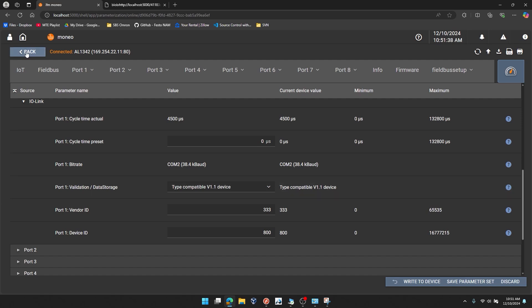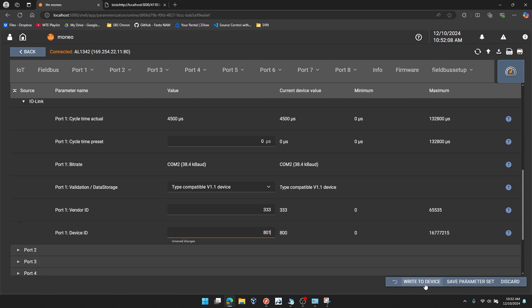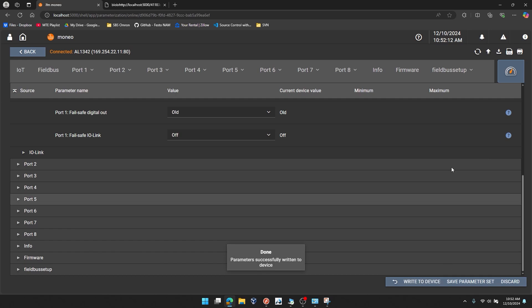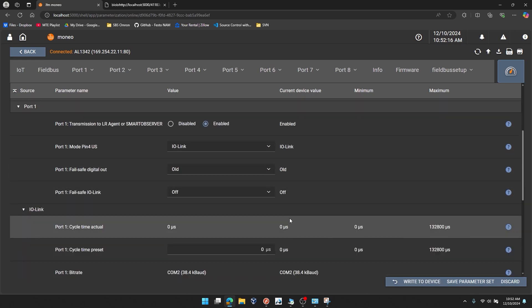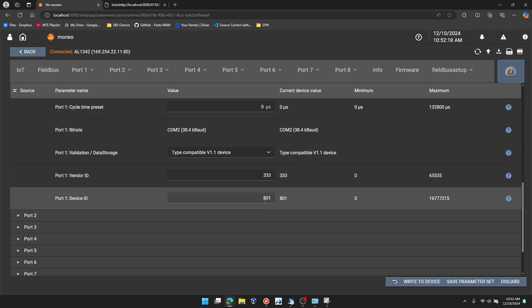The next thing I'm going to show you is how to use this device validation here under the port one IO-Link settings to confirm that you have the right device connected and any off-the-shelf maintenance replacements of your valve terminal need to be the same vendor ID and device ID to be connected to this port. So for a quick example, I'm going to change this device ID to 801, which is incorrect for the VTUG valve terminal we have connected.